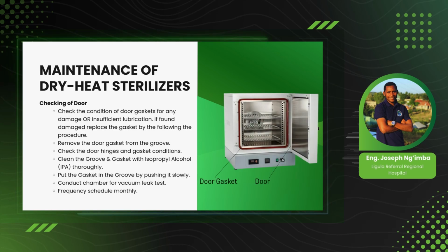Let's start with the maintenance. We do maintenance to make sure the machine is kept in its normal operation and gives us the required results. So what is being done in maintenance? We check some parameters. The first thing to check is the door. We check the condition of the door gasket. The purpose of the gasket is to ensure the door seals intact to reduce heat loss, so it is important to check the gasket. If there is any damage, you have to replace it.